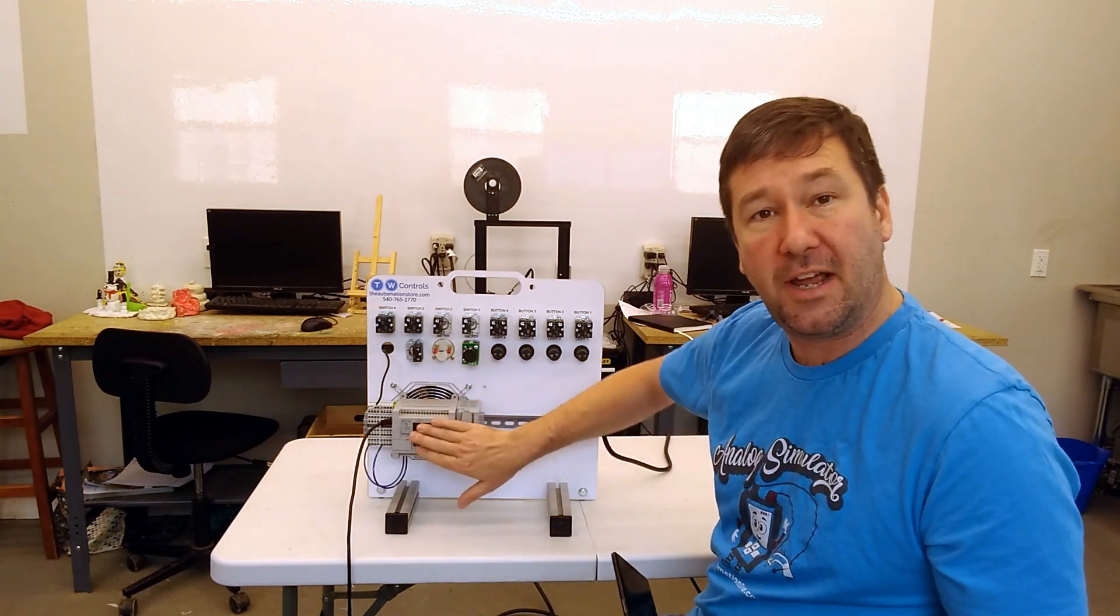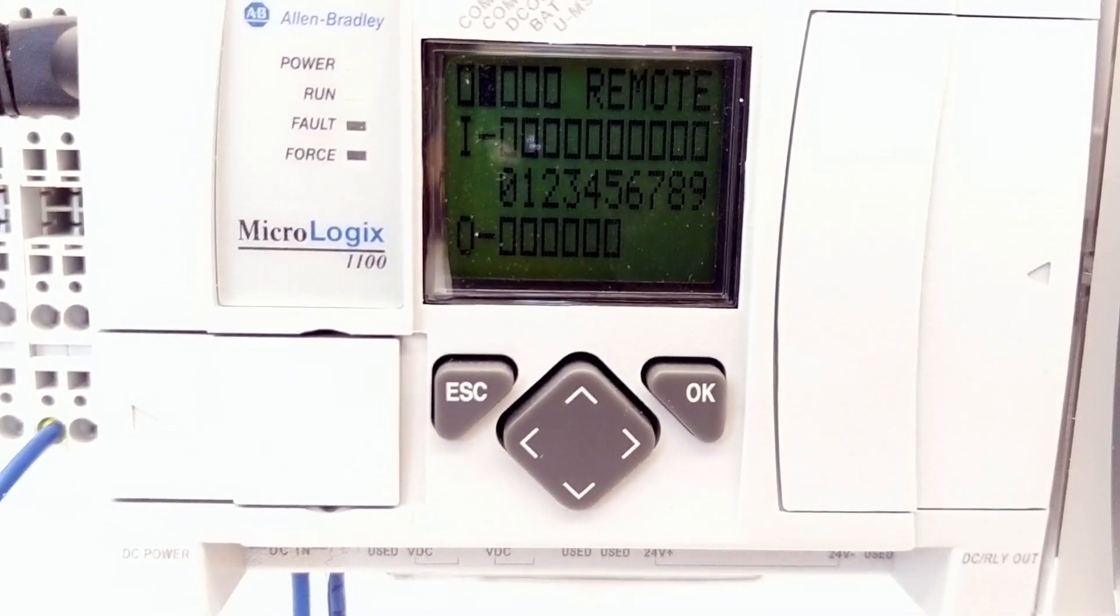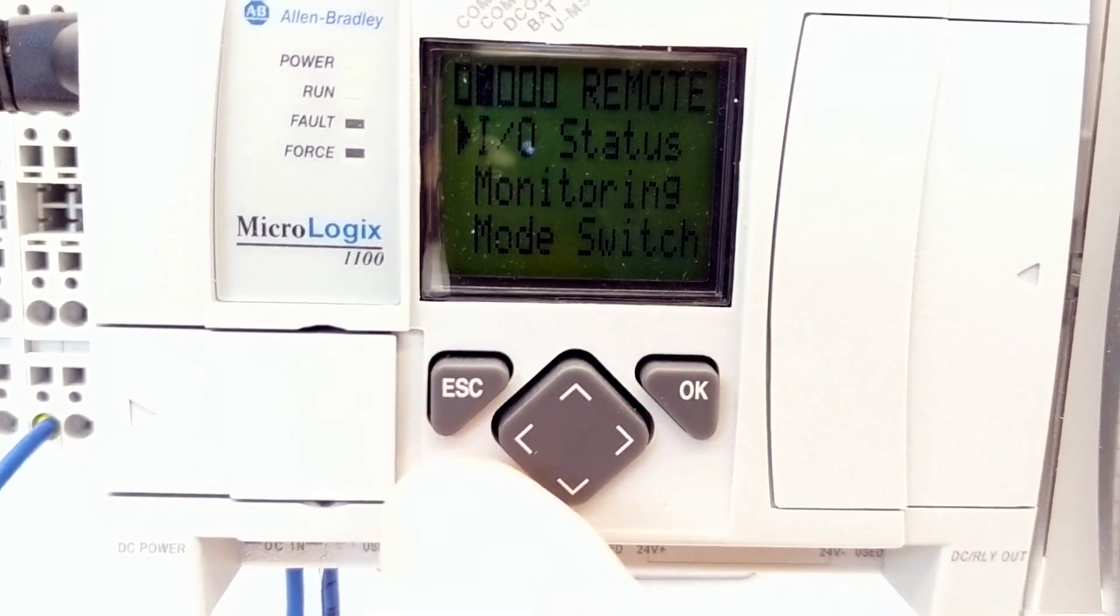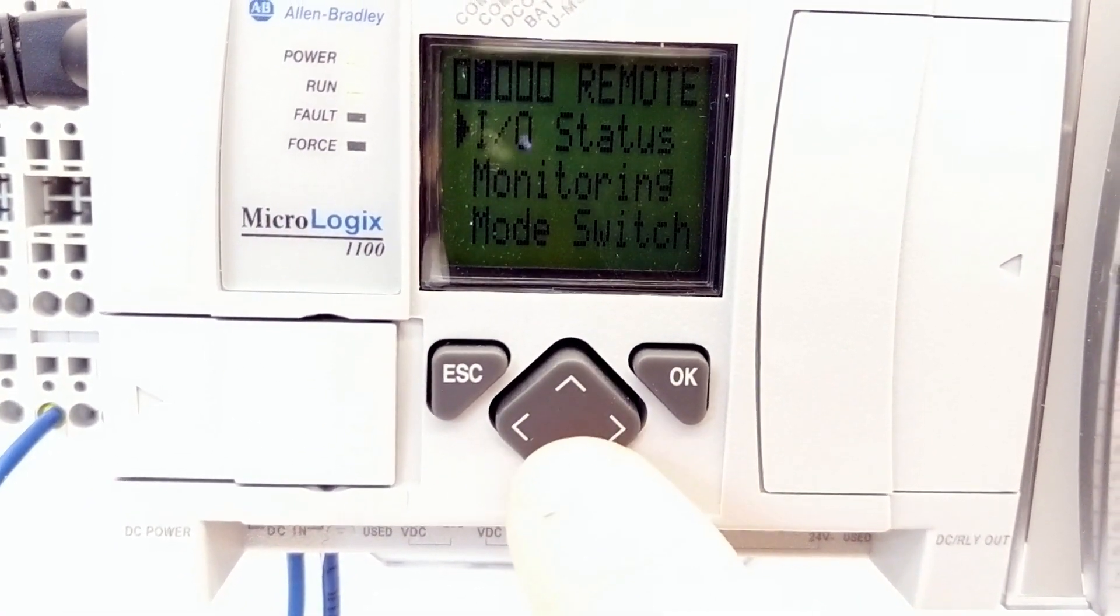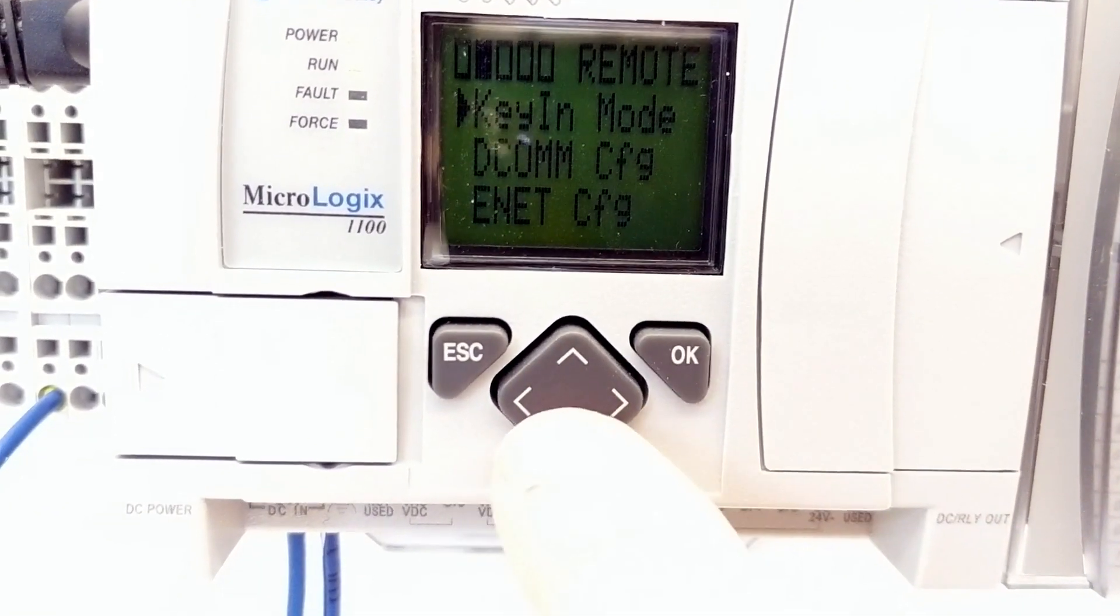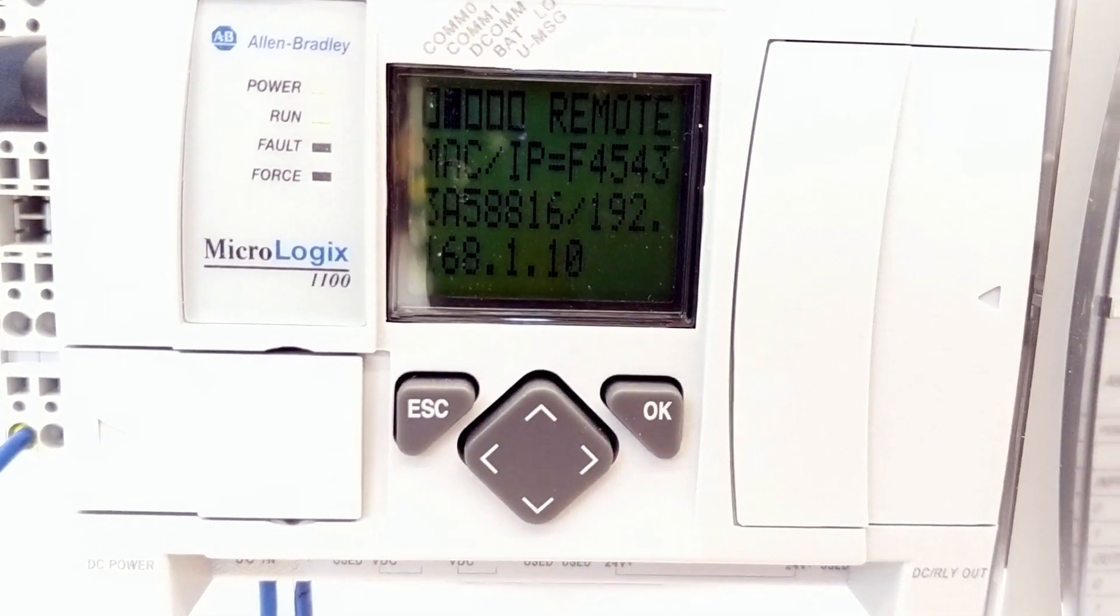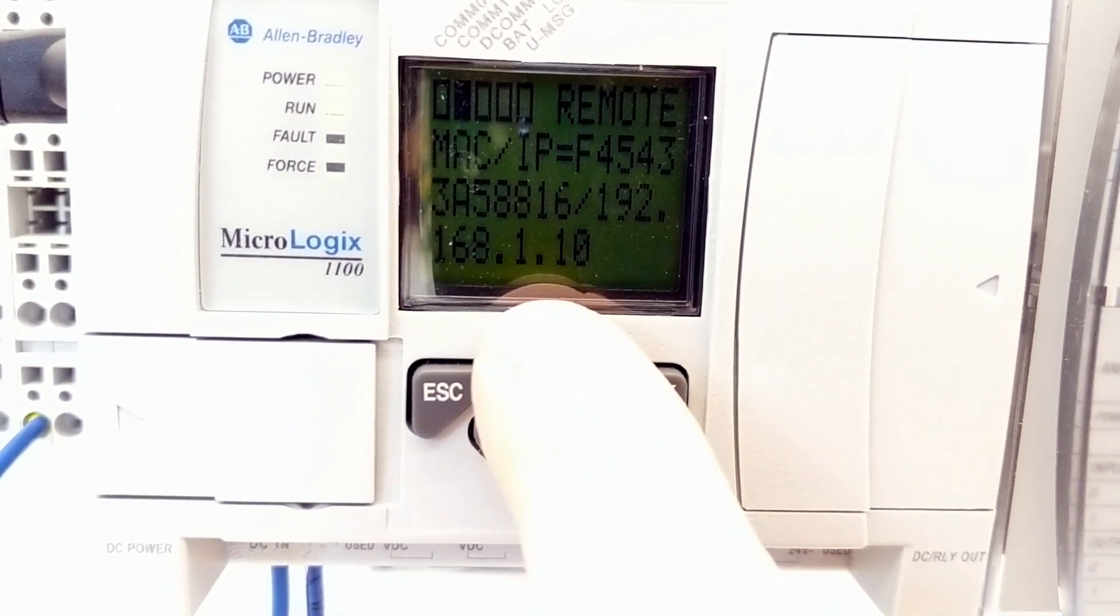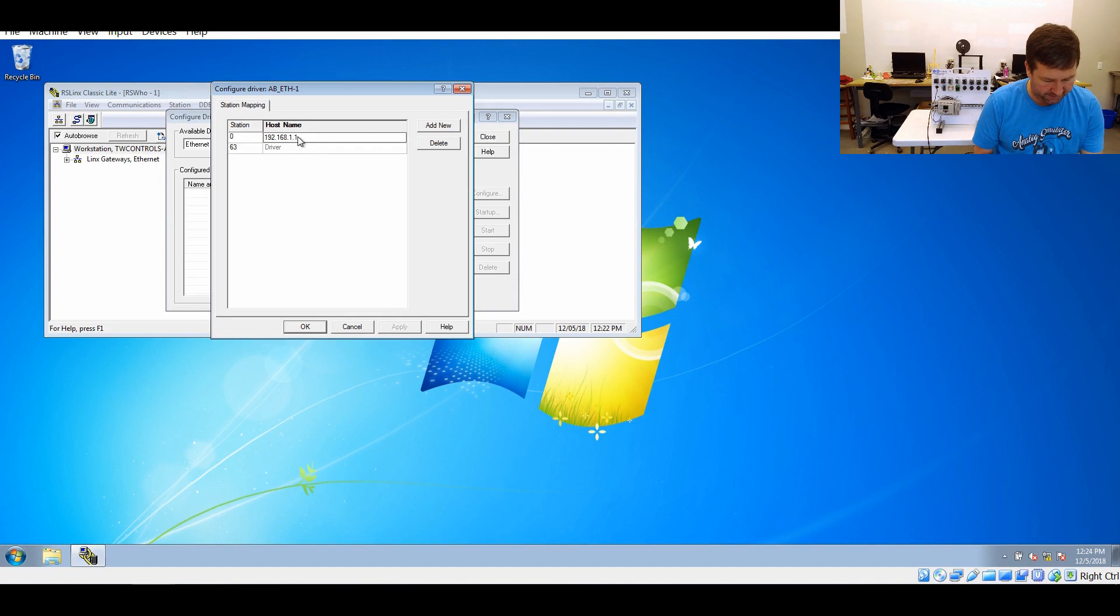Now if you have 1100, you can actually do it from the front display. Here is the default display of the MicroLogix. We're going to click the escape button, and that'll bring us to the main menu. It starts with IO status. We'll scroll down and find advanced settings, then click OK. Then we're going to scroll down to enetconfig and click OK. You can see right here, the IP address is 192.168.1.10. So we're going to type that IP address right here, 192.168.1.10, and click OK.